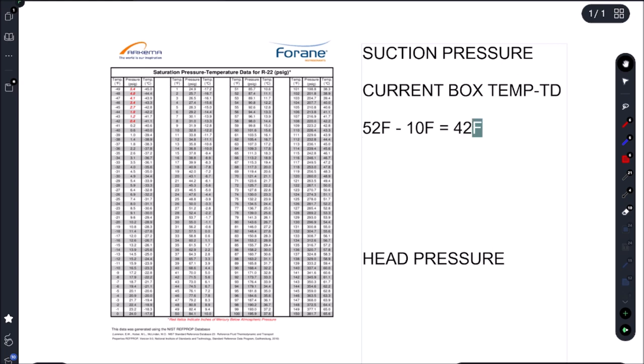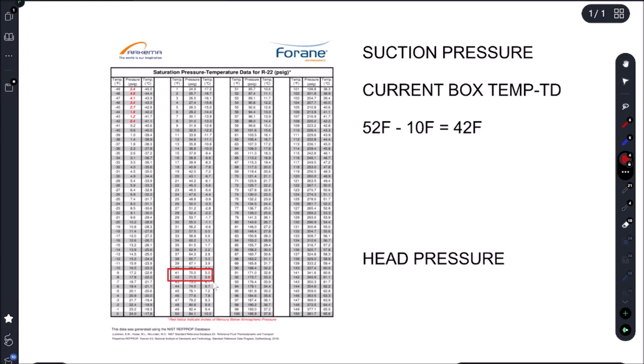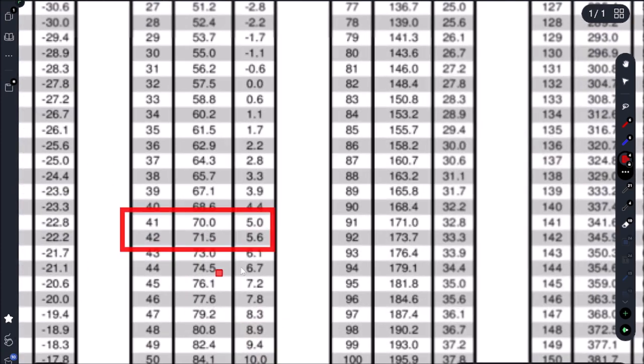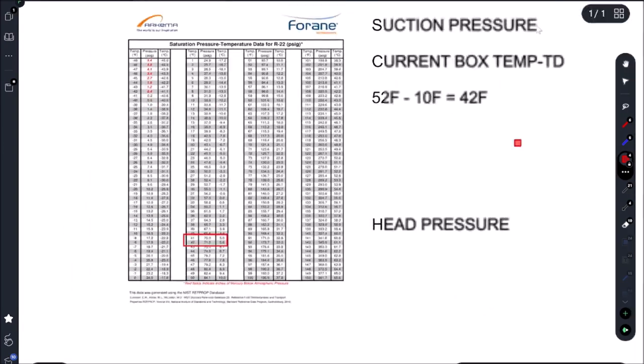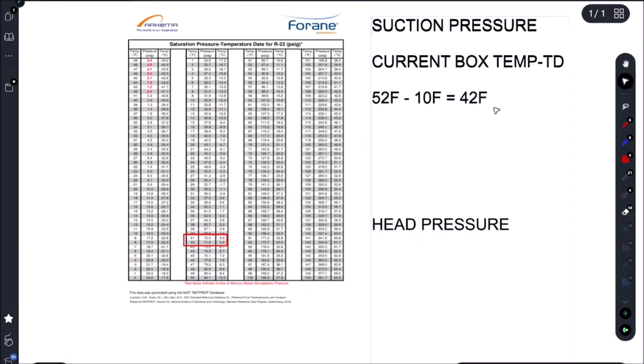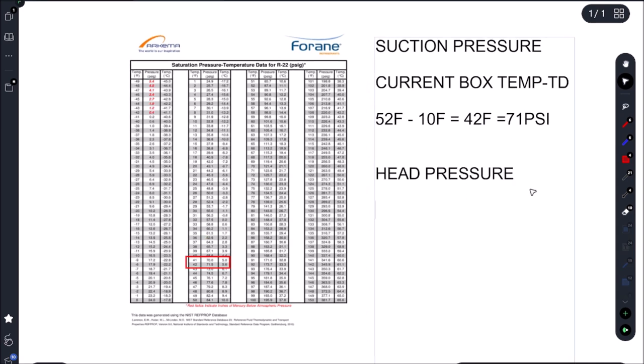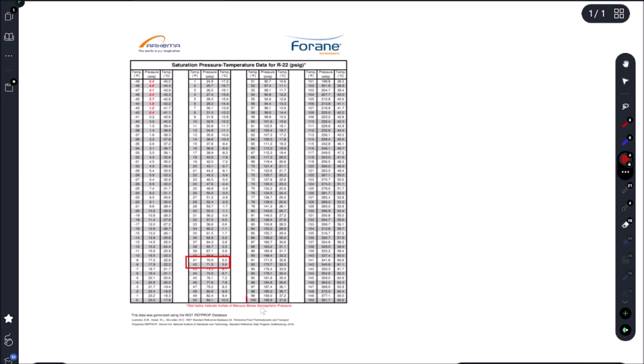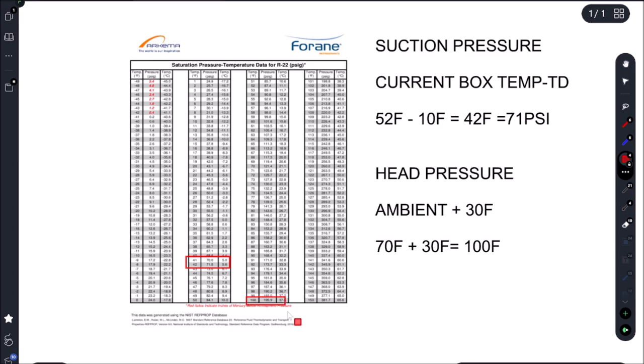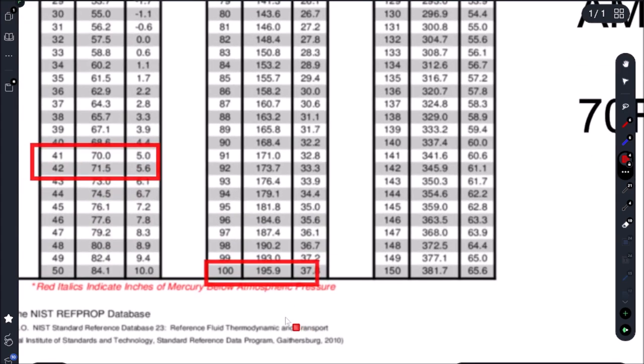So that is our saturation temperature. That's what we want to focus on but we'll still use the chart. Where we need the chart is because we want to figure out if we have high pressure or low pressure, but you could use high temperature, low saturation temperature, it's all the same. So if we go look up 42 Fahrenheit, that's giving us 71 psi. And for our head pressure we just simply take our ambient and we're going to add our engineered condenser split which in our case is a 30 Fahrenheit condenser split. So we have around 70 Fahrenheit, we're going to add 30 Fahrenheit and that's going to give us 100 Fahrenheit. 100 Fahrenheit gives us 195 PSI.